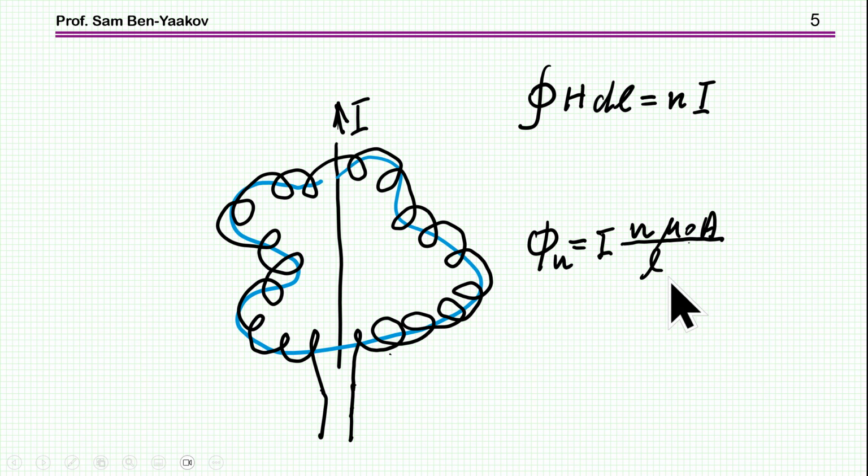So this is the beauty of the Rogowski coil. You don't have to have the wire going into the middle of this loop. It can be anywhere, theoretically at least. There are some parasitic effects, of course, so it's not exactly that you get exactly the same value, but it's pretty close that you can actually wrap the coil around anywhere, and you get the correct value.